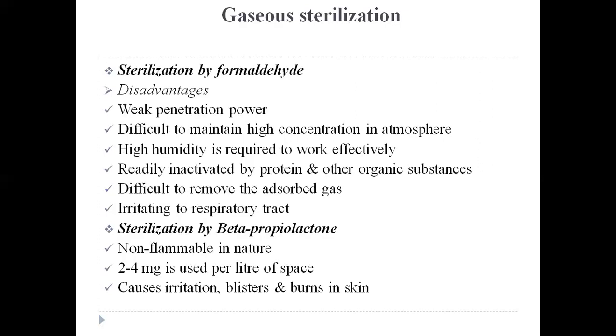There are many disadvantages of formaldehyde compared to ethylene oxide, and some of them I have given over here. First, compared to ethylene oxide, formaldehyde has weak penetration power, which is a major drawback. The next thing is, we have to maintain a higher concentration of formaldehyde in the atmosphere, which is very difficult to maintain. The next is, it needs a higher humidity for efficient sterilization of any substance, which again is difficult to maintain everywhere.